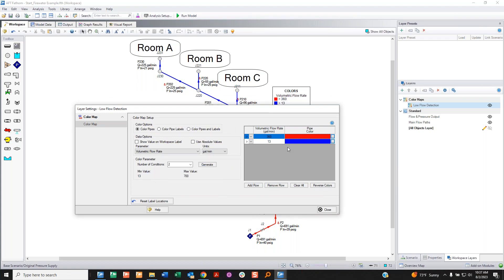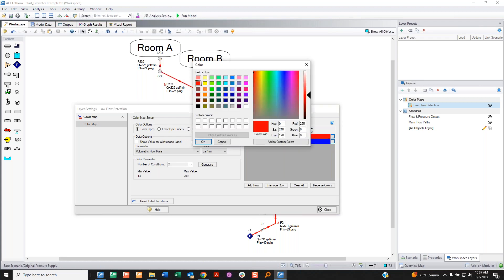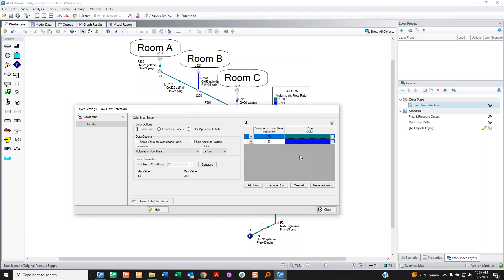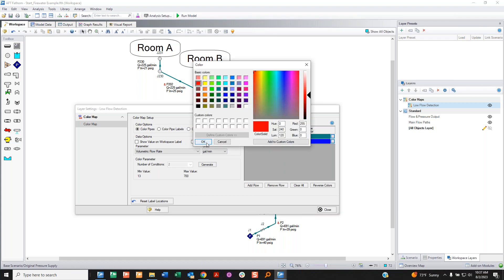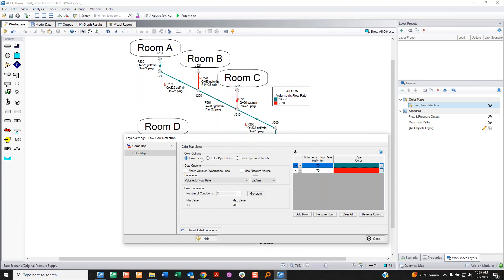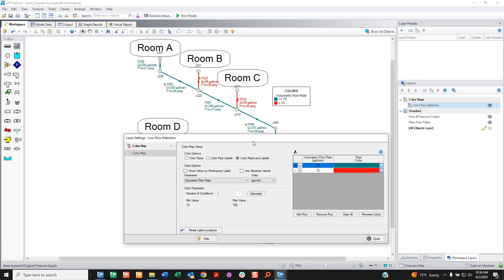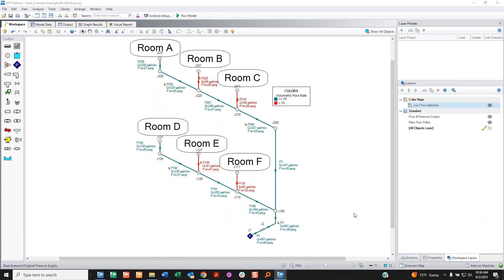I only want two thresholds. Anything above 360 will be one color, anything below but above another threshold will be blue — that's the automatic version based on min and max values. But I want to customize it: anything above 70 gallons per minute should be green, meaning it's good; anything less than 70 should be red because that's below my threshold. I choose my colors, choose my thresholds, and then I color both pipes and labels so it's really obvious to the human eye.